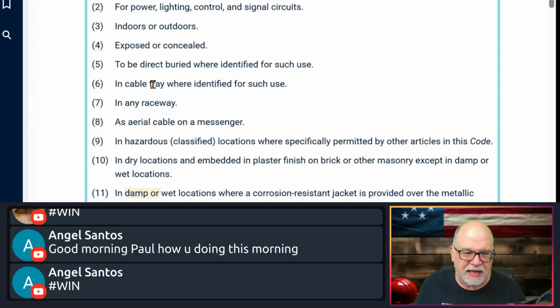The next is to be direct buried where identified for such. So again, if it's got direct burial written on it, or DB written on it, then it's rated to be direct buried. I can tell you PVC jacketed MC will, in most all cases, have the markings on it for it to be direct buried. In cable tray where identified for use, so it has to have that marking on the side that says for CT use. That just means that it went through some extra testing to be able to have a horizontal flame test, that type of thing. So it meets that rule. It's 1685, a UL standard for flame propagation and all this kind of stuff. You know what I'm saying?